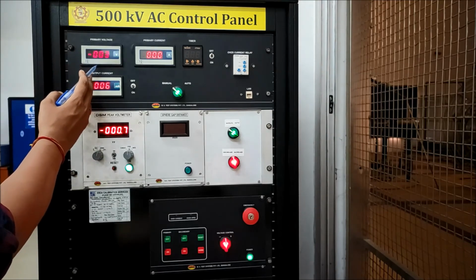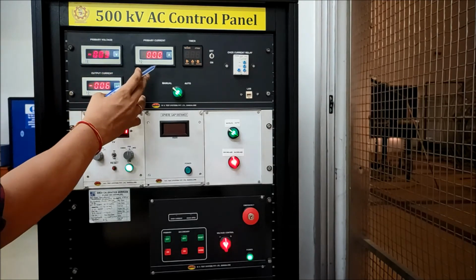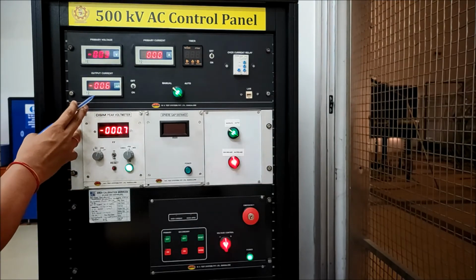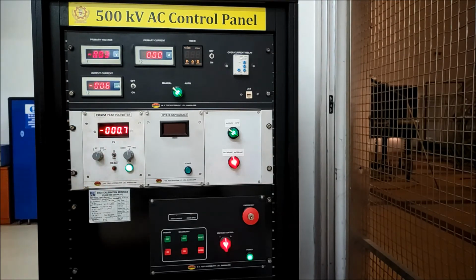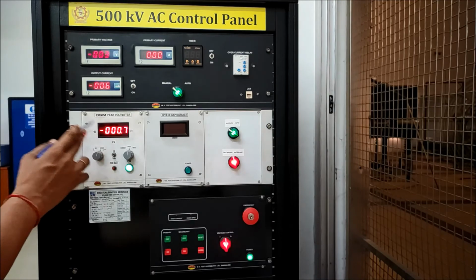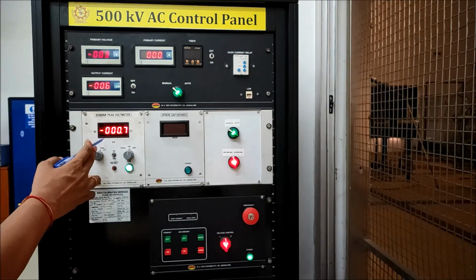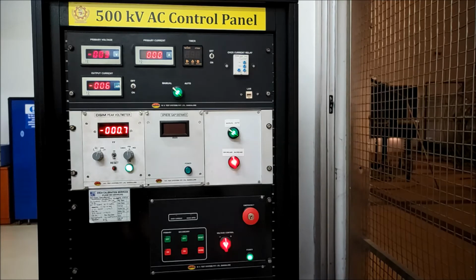This is the primary voltage. You can see here, this is the primary current, this is the secondary current, and this is the secondary voltage. This secondary voltage means the transformer output voltage, or the voltage across the whole string. This is the voltage across the whole string, not the sphere gap voltage. How to calculate the sphere gap voltage? I have already explained.